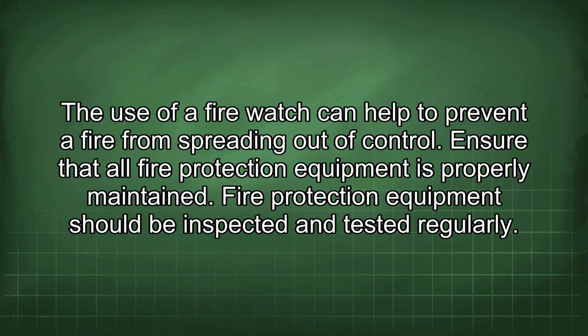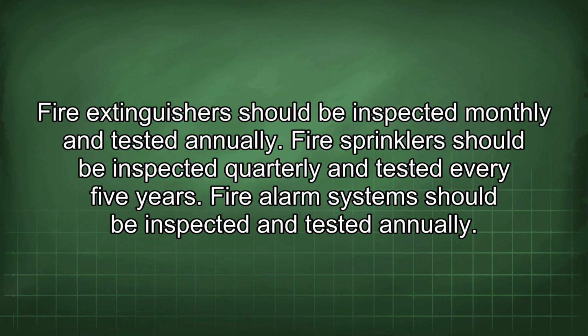Ensure that all fire protection equipment is properly maintained. Fire protection equipment should be inspected and tested regularly. Fire extinguishers should be inspected monthly and tested annually. Fire sprinklers should be inspected quarterly and tested every 5 years. Fire alarm systems should be inspected and tested annually.